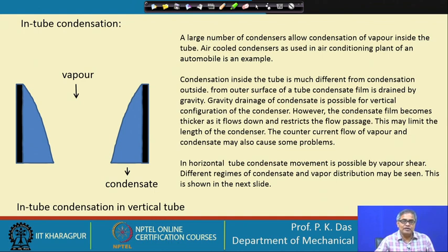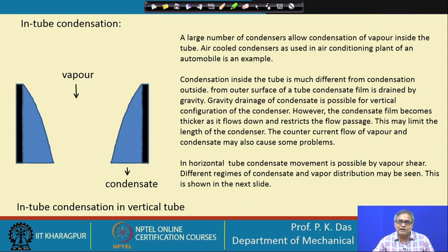In vertical tube condensers, in-tube condensation takes place inside the vertical tubes, and on the shell side there will be coolant. The vertical tube configuration is very good because gravity helps to drain out the condensate. Whenever we think of filmwise condensation, film drainage is one of the key issues, and gravity is the best method for film drainage.